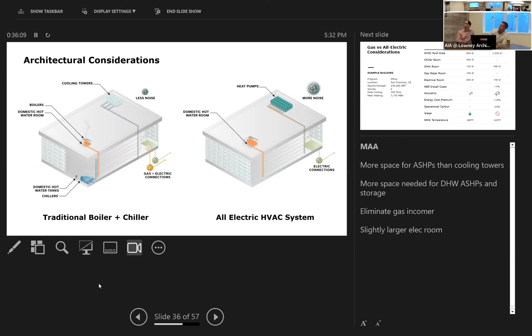And this is just a little table that shows some spatial comparison. So we took a typical San Francisco office building, 250,000 square feet, 6 stories, 500 tons of cooling, 3,750 MBH heating. And we worked up some space requirements. So on the roof, for the all-electric air source heat pumps, we've gone from 850 in the traditional case to 1,250. The chiller room has gone, as I mentioned before. The domestic hot water room's got bigger with all-electric because of the larger requirement for storage. The gas meter room has gone. Your peak electrical load with all electric is going to go up a bit. Not as much as you think, but it does go up a bit. So we've got a slightly larger electrical room.